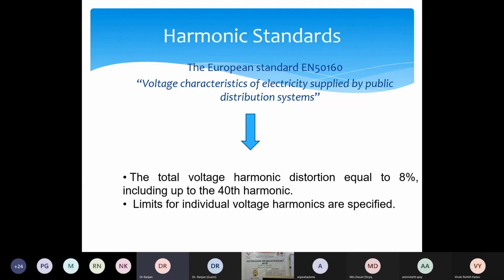So total THD must be equal to 8%, including up to 40th harmonic. For example, 40th harmonic means 40 into 50, in India, that order harmonic should be within that, total must be 8%.